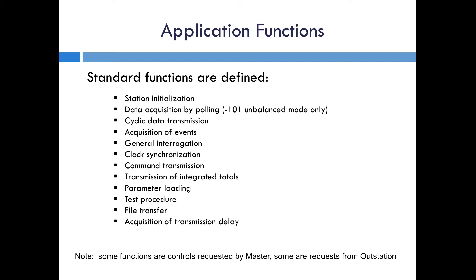General interrogation is the equivalent of the class zero poll in DNP3. The master can request a clock synchronization and can send commands to the outstation. There's a way for sending integrated totals or counter measurements, parameter loading which allows the master to send certain parameters to the outstation, testing requests, file transfer requests, and requests to acquire the transmission delay. Some of these are control requests from the master, some are from the outstation — I'm just going to go over a few of the more important ones.